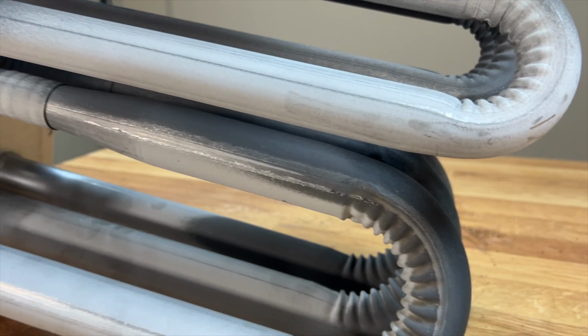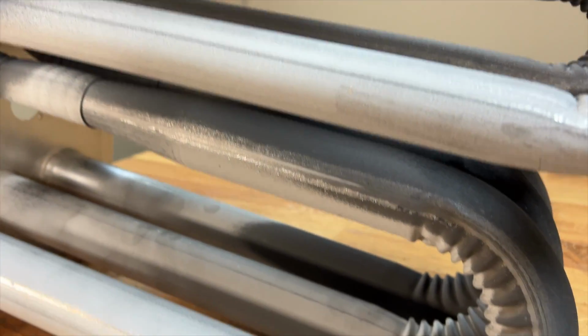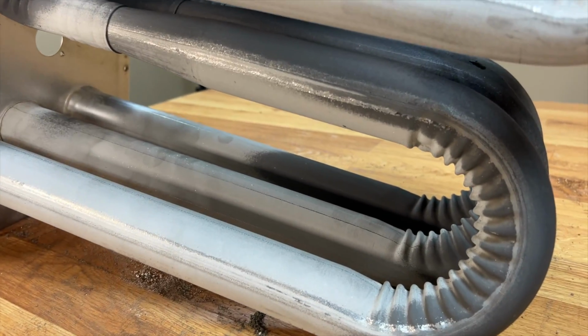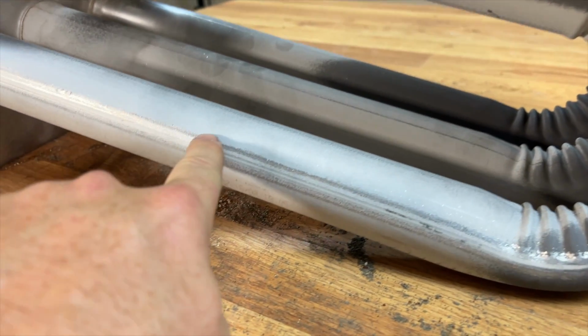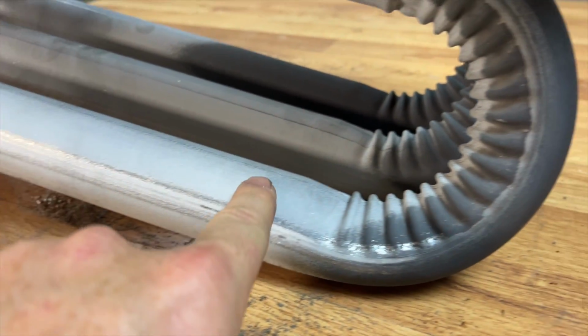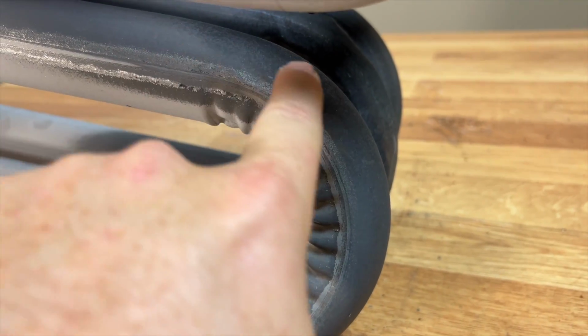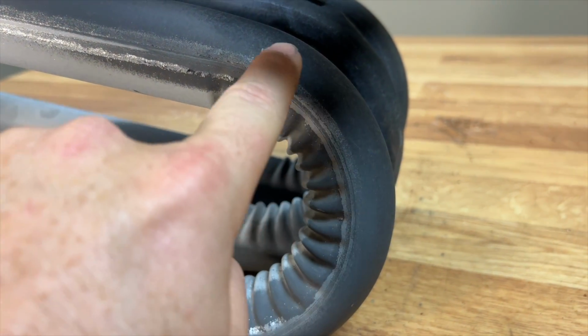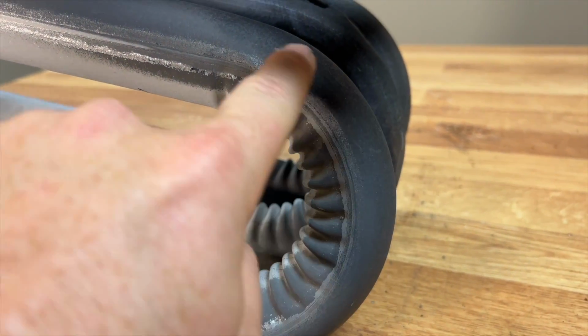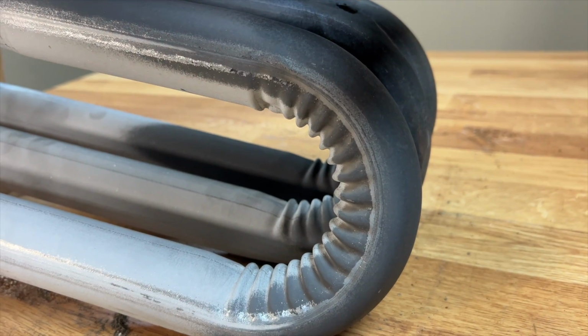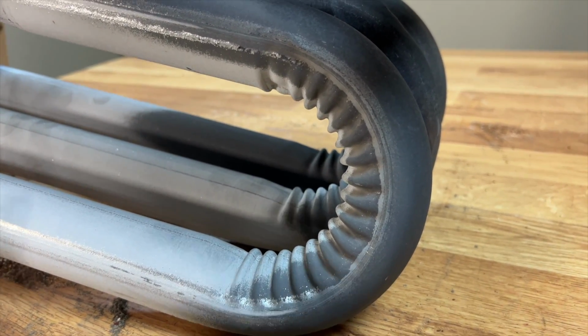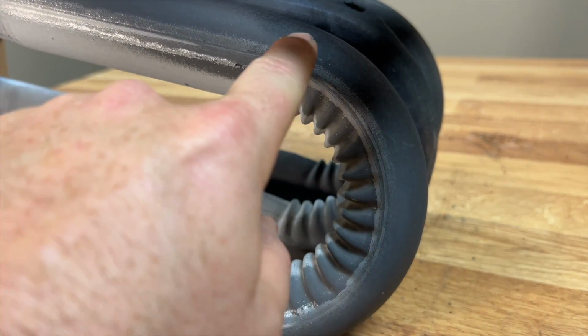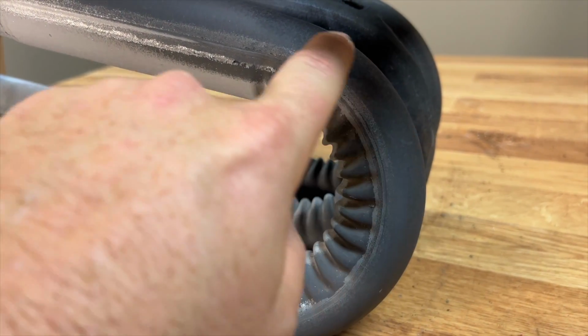Now, when we're looking at heat exchangers, we're looking for cracks, we're looking for holes, right? Well, what's an indicator of a crack going to form? Well, as you can see here, this is the normal color of a heat exchanger. You see how it gets really dark right here? Well, that's a sign of temperature stress. This is what we call a temperature stress point. Now, even new furnaces will have them. It's totally normal. It has to do with the heat moving through.